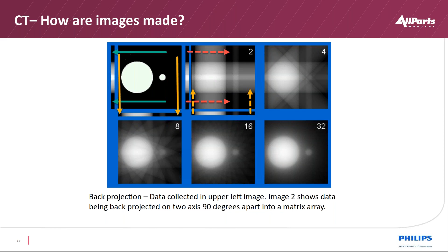So it was realized that we have to have some type of frequency response filter to clear up the image. With that, we have what we call basically a fast Fourier transform, FFT, as it's known. It takes the data set from the view that you see over on the far left side. We then transform it with a filter. A smooth filter means we're looking for small changes. A sharp filter would be for something like a bone, air, bone, soft tissue transition. So we can enhance the data set by frequency.